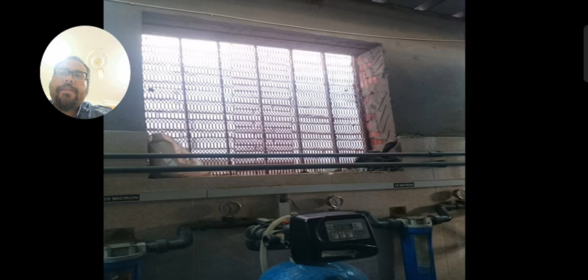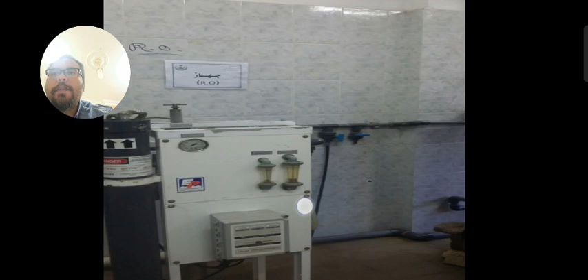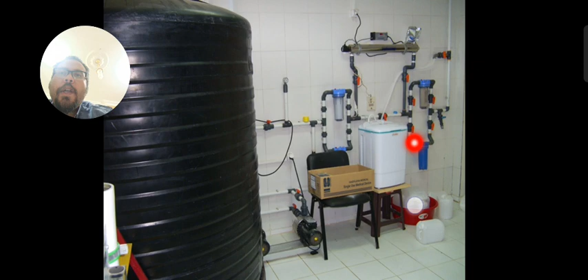Also, the water treatment unit must be closed, not open like this. It must be closed, and we put air conditioning or a fan only, not open to the outside. Also, mixing bicarbonate inside the water treatment unit is wrong.